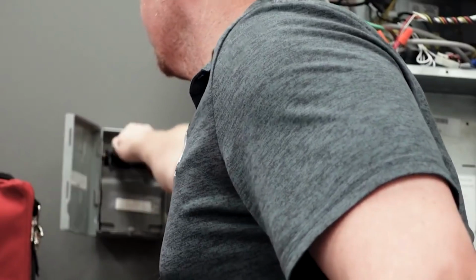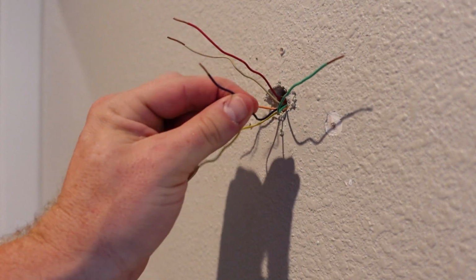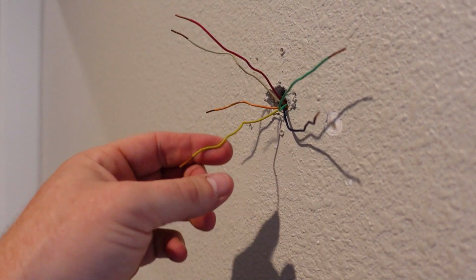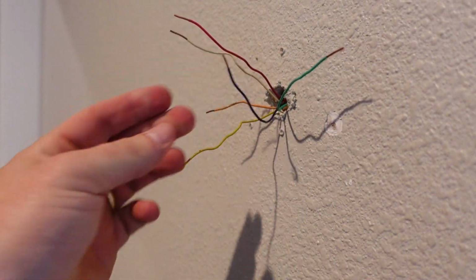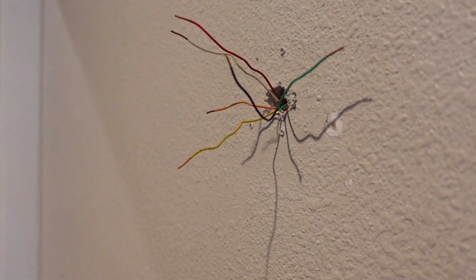All right, so the first thing you have to do when you're installing any thermostat is you have to shut off the power. So we're gonna shut off the disconnect. I'm gonna go in and identify all of my conductors. We have all of the common kind of conductor colors. You have your red, which is your constant 24 volt power. You have your blue, which is your common. If you don't have a common, you can rely just on battery backup.